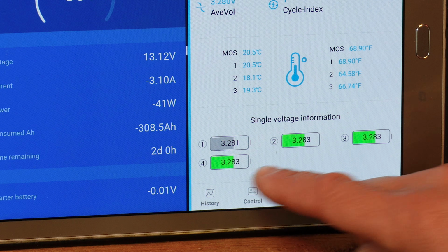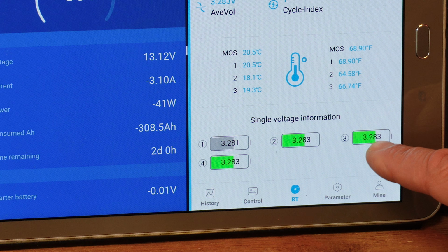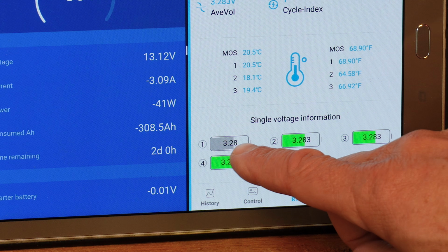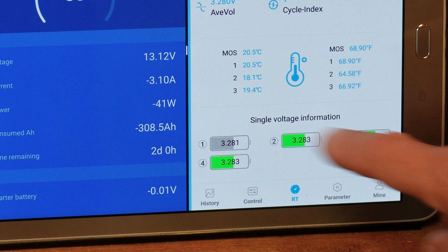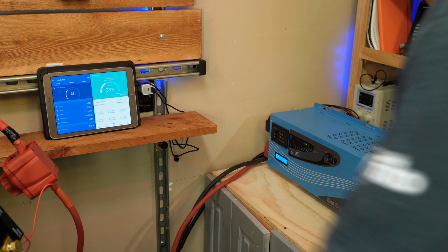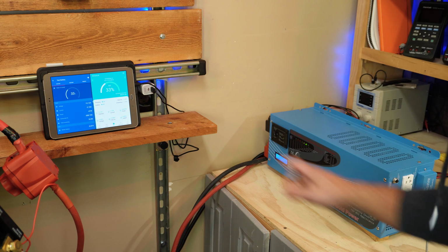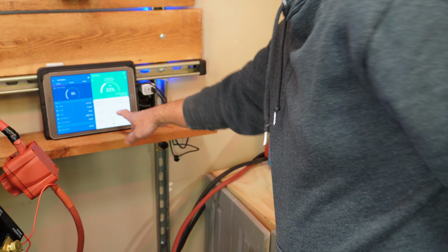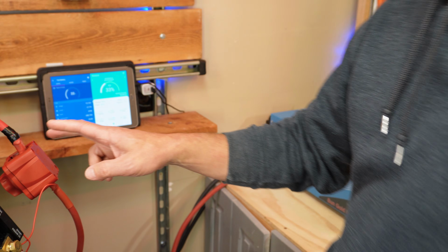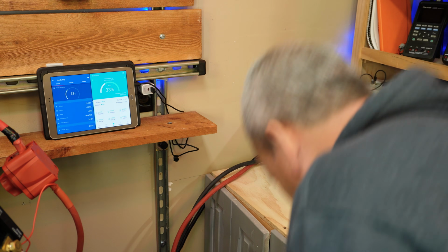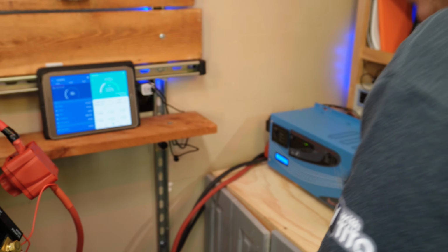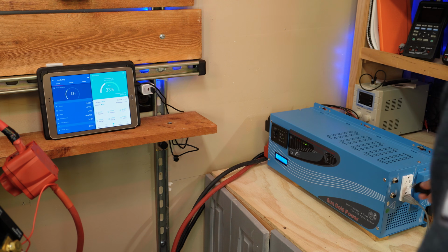They're pretty well balanced at 3.28, 3.28, 3.28. So the first thing we'll do is test the 250 amp output of the BMS. It should shut down or disconnect power once we hit that 250 amp rating.